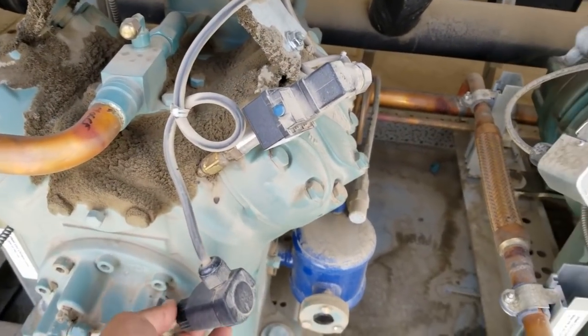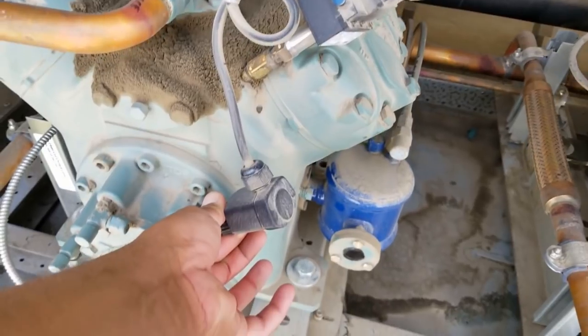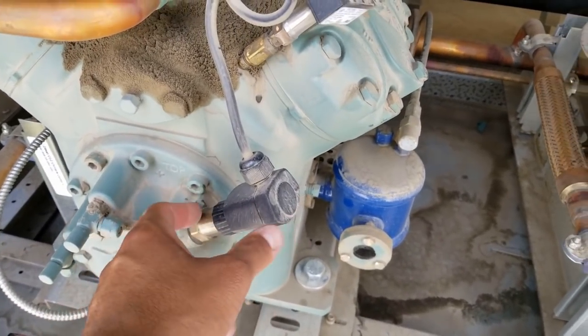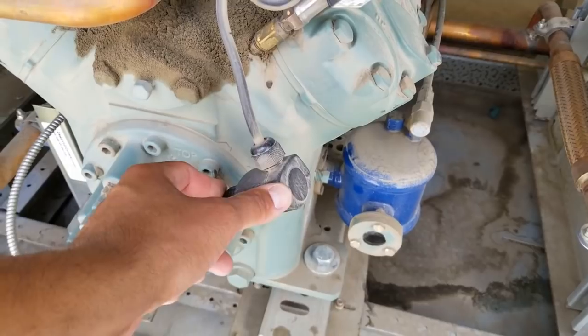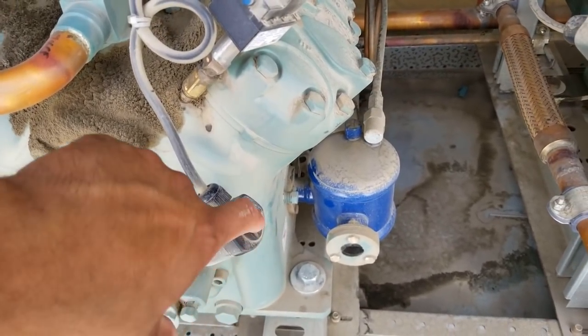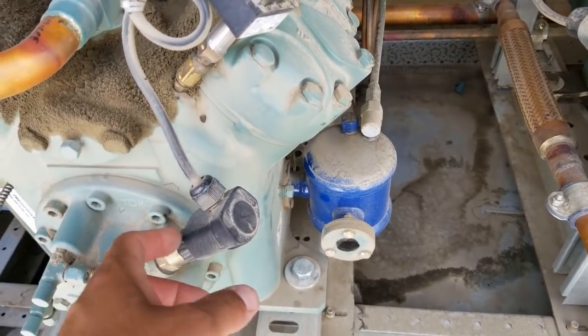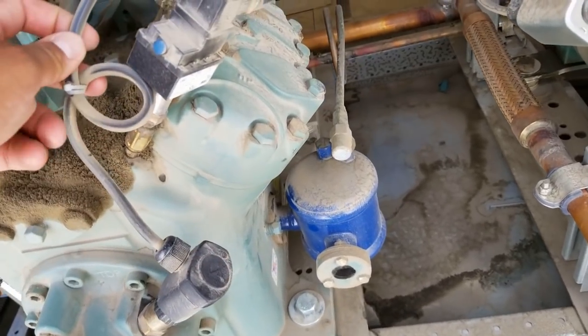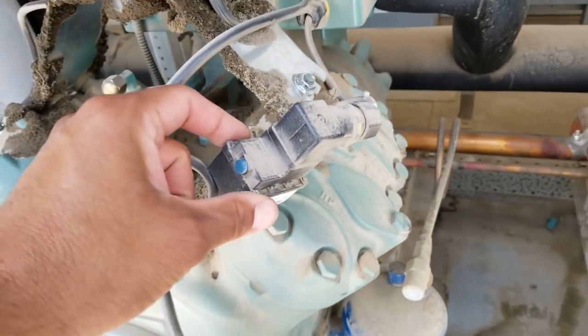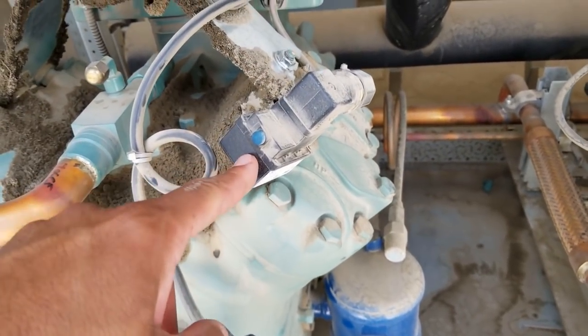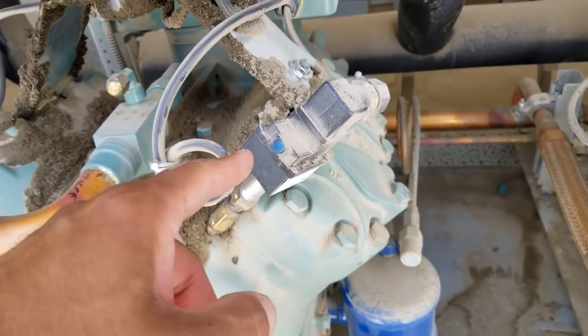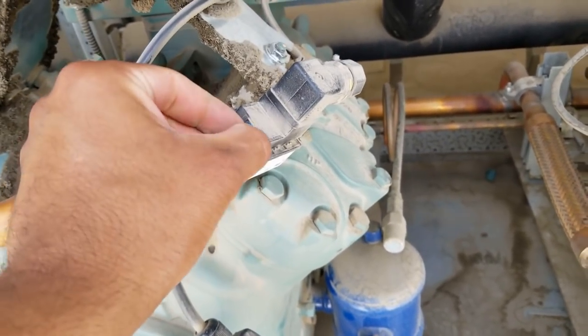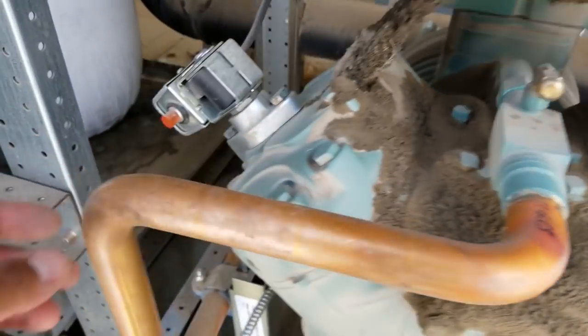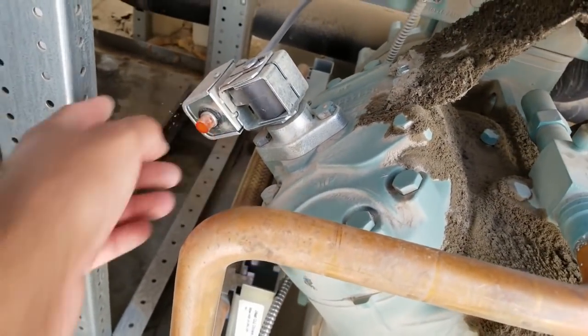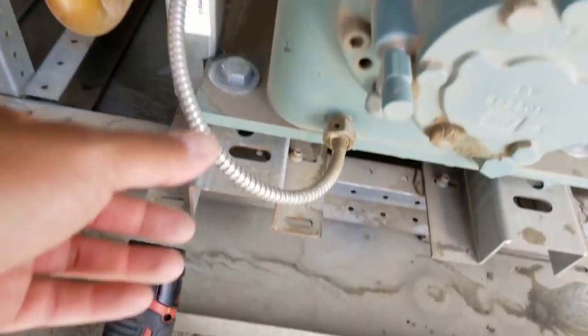So this is the oil fail control here. And there's two different types, and they look exactly the same. There's one that has a reset button right on top, and the other one, of course, does not, like this one. So these are tied into the box. And you got your high pressure control, which is your blue button here, which is not the problem. And you got your unloader on one of the heads. And what else you got? You got your crankcase heater and your oil float.